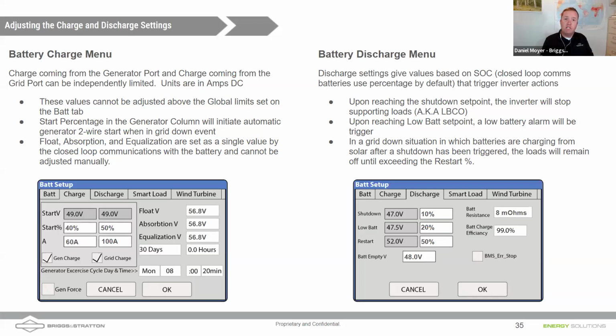The inverter is going to stay on, and we want some juice left in the battery to keep the inverter on, so that if solar does come back out, if the grid comes back, well, the grid would turn the inverter on anyway, but you want to leave a little bit in to account for the parasitic draw of the inverter. All right, grid's back. Solar's producing. The loads aren't going to turn right back on. We want to let that battery get a good charge, maybe up to 50%, which is what I have here, before we restart supporting the loads. Andrew, what do you think about the values I have here, and do you have any suggestions?